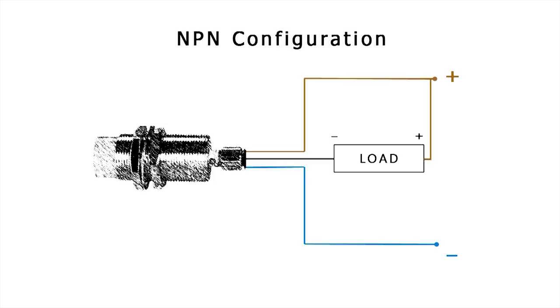For NPN connections, the output wire will now connect to the load's common and the wire connected to the positive side of the power supply will need to be electrically connected to the positive side of the load.